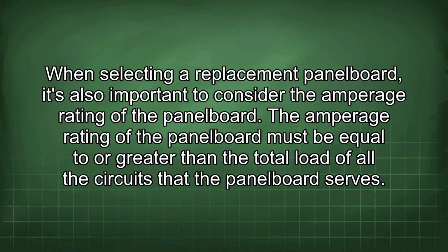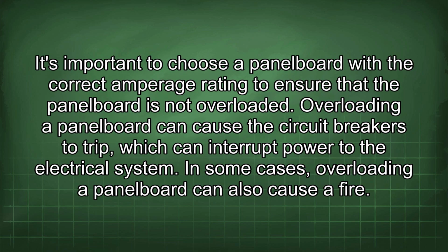When selecting a replacement panel board, it's also important to consider the amperage rating of the panel board. The amperage rating of the panel board must be equal to or greater than the total load of all the circuits that the panel board serves. It's important to choose a panel board with the correct amperage rating to ensure that the panel board is not overloaded. Overloading a panel board can cause the circuit breakers to trip, which can interrupt power to the electrical system. In some cases, overloading a panel board can also cause a fire.